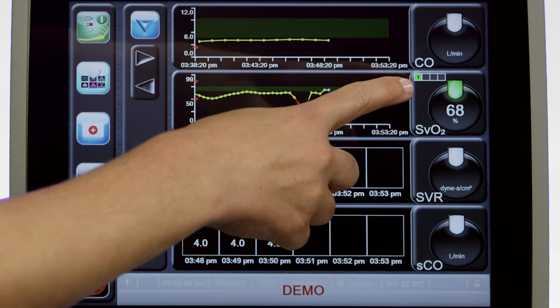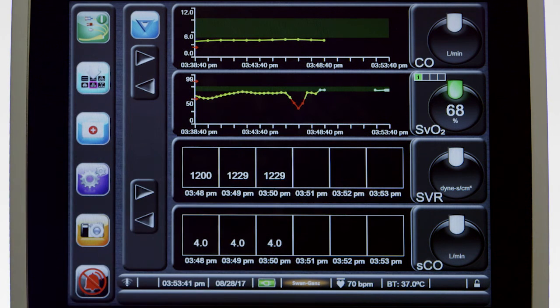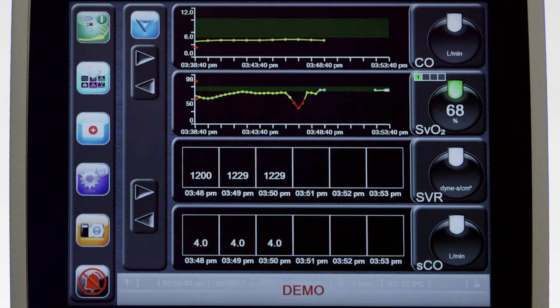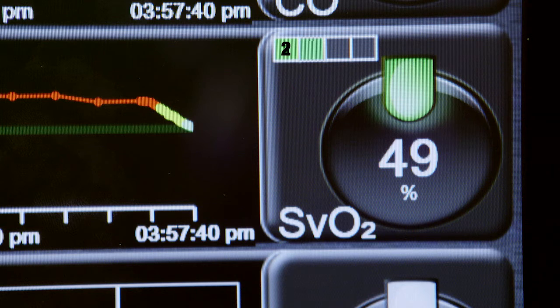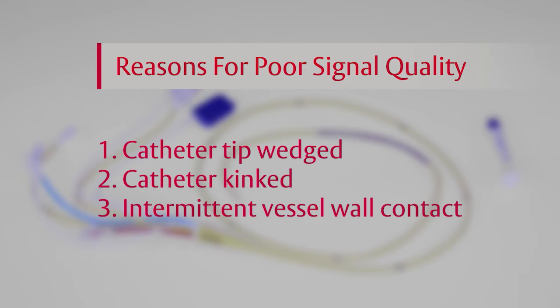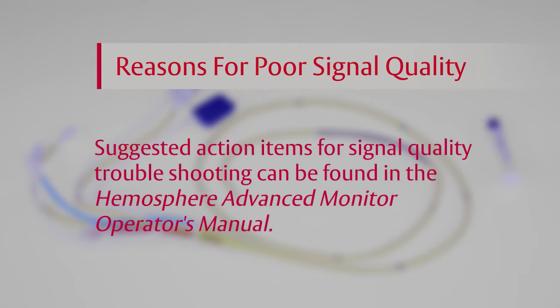Notice the signal quality index on the SVO2 parameter globe. This graphic represents the quality of the signal coming from the tip of the catheter. If the icon displays 1 or 2 green squares, then there is a strong signal coming from the catheter. A yellow or red icon indicates a problem with the catheter signal, and you should take action to determine the cause of the poor signal. A few reasons why the signal quality may be compromised can be due to the catheter tip being wedged, the catheter being kinked, or intermittent vessel wall contact. Suggested action items for signal quality indicator troubleshooting can be found in the HemoSphere Advanced Monitor Operator's Manual.